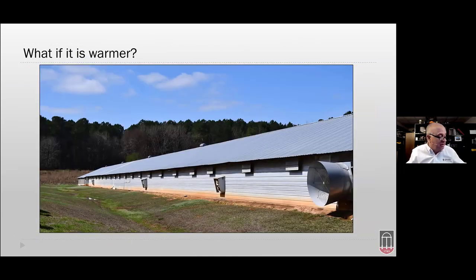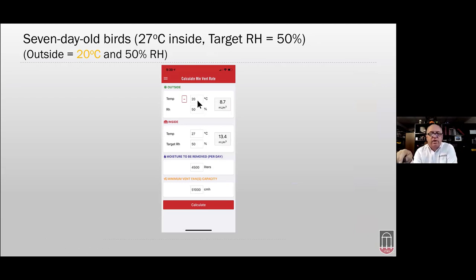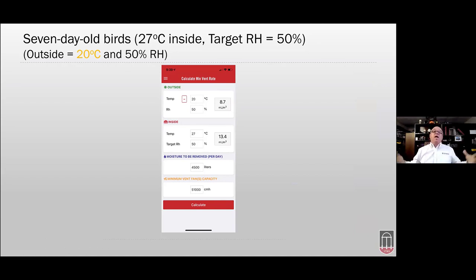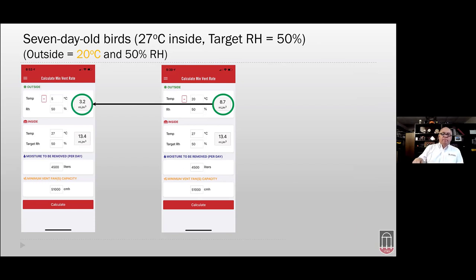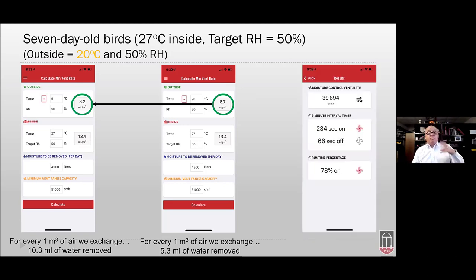What about warmer climates? Change the outside temperature to 20°C at 50% humidity with the same inside conditions. At 20°C and 50% humidity, there's 8.7 milliliters of water per cubic meter of outside air — much more than 3.2 at 5°C. There's less of a difference between inside and outside, so for every cubic meter exchanged we're only removing 5.3 milliliters, versus 10.3 before. When it's 20°C outside, minimum ventilation rates essentially have to double to remove the same amount of moisture.